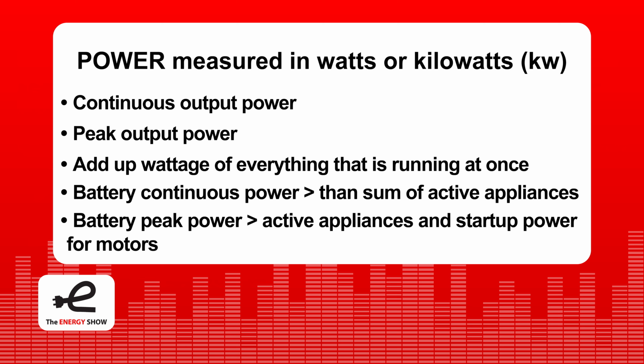In addition, the peak output power of the battery, also on the specs, has to be greater than all your active appliances plus the startup power for all your motors. This is usually the tricky part—not having enough battery peak power. Newest systems have a really high peak power output, but some older ones don't.